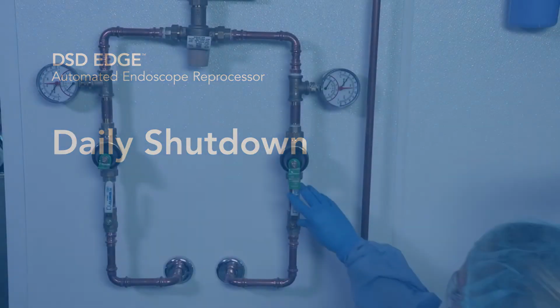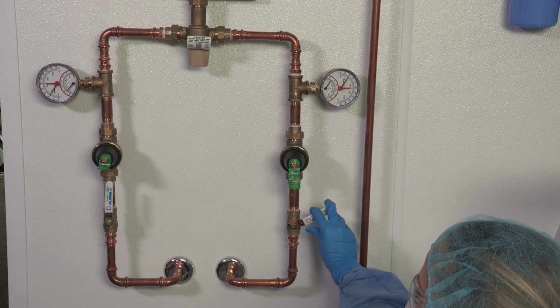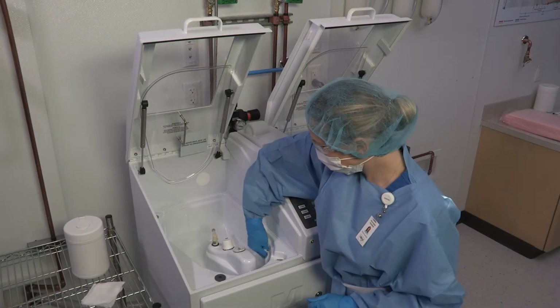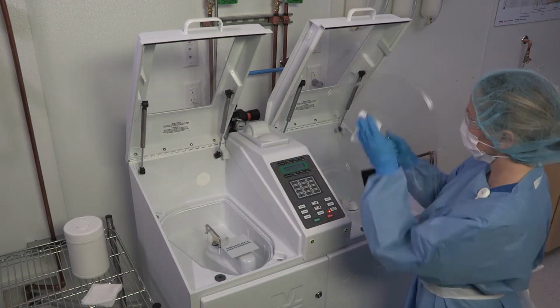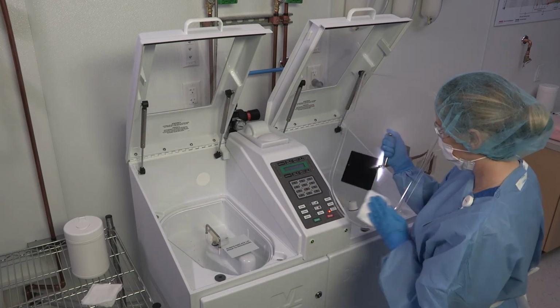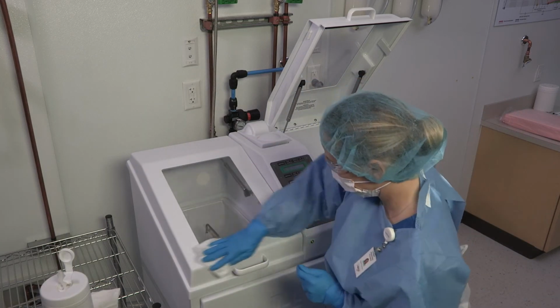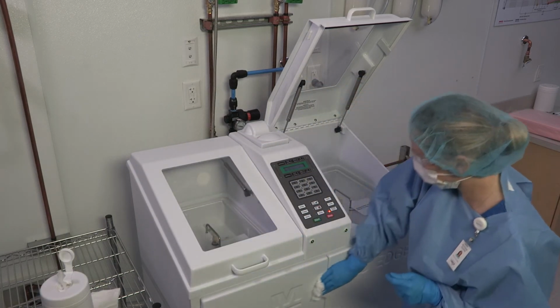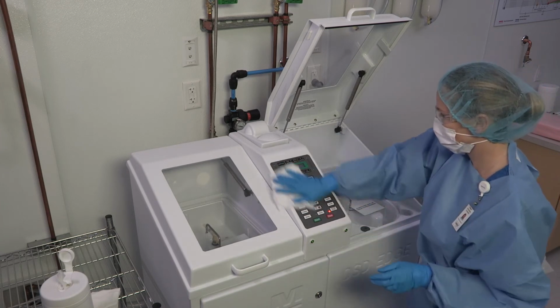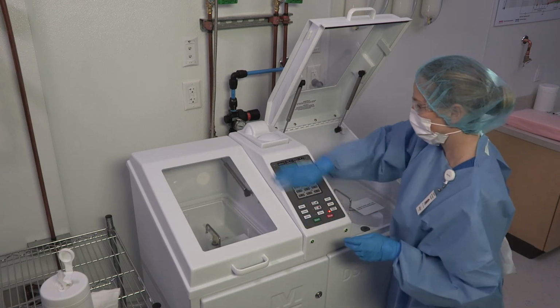At the end of the day, close the incoming waterline valve. Wipe out the inside of the basins and under the floating lids with a clean, unused, lint-free cloth. Disinfect the outside of the machine, basin lids, top of floating lids, and the barcode scanner with EPA-registered surface disinfectant wipes.